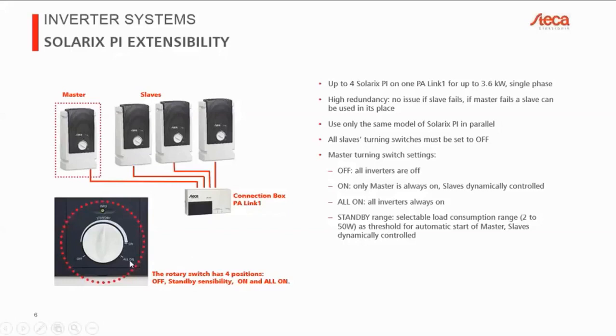Then there's another one which is all on, so you can probably guess. This means that all of the inverters are always running. Honestly, I don't think I've ever had a customer who has needed that setting. If for some reason you have very extreme peaks, it could theoretically happen that the system is not capable of activating the slaves in time. To be honest, very unlikely, because I think it takes about half a wave to activate them, because it always happens at the passage through 0. But if for some reason you do have issues, for example, if you have an industrial estate with large machines, that kind of thing, you could also have them all running all the time.